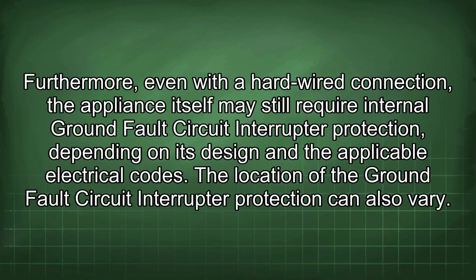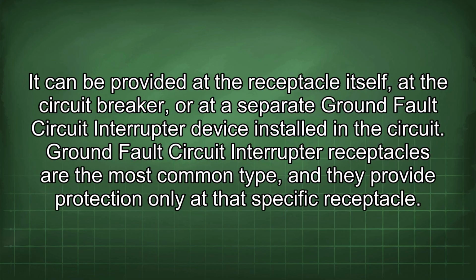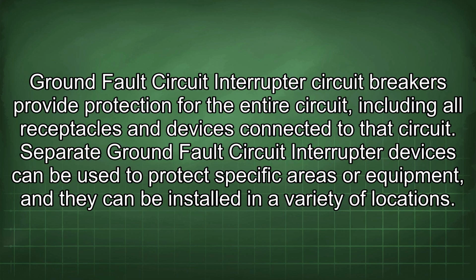The location of the ground fault circuit interrupter protection can also vary. It can be provided at the receptacle itself, at the circuit breaker, or at a separate ground fault circuit interrupter device installed in the circuit. Ground fault circuit interrupter receptacles are the most common type, and they provide protection only at that specific receptacle. Ground fault circuit interrupter circuit breakers provide protection for the entire circuit, including all receptacles and devices connected to that circuit. Separate ground fault circuit interrupter devices can be used to protect specific areas or equipment, and they can be installed in a variety of locations.